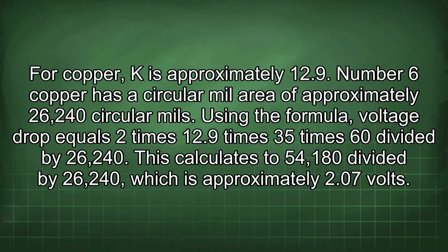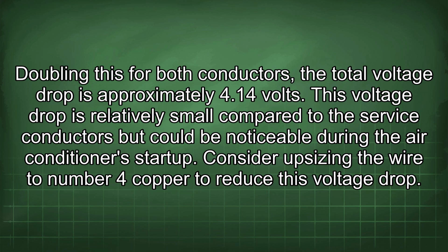Number 6 copper has a circular mil area of approximately 26,240 circular mils. Using the formula, voltage drop equals 2 times 12.9 times 35 times 60 divided by 26,240. This calculates to 54,180 divided by 26,240, which is approximately 2.07 volts. Doubling this for both conductors, the total voltage drop is approximately 4.14 volts. This voltage drop is relatively small compared to the service conductors but could be noticeable during the air conditioner startup. Consider upsizing the wire to number 4 copper to reduce this voltage drop.